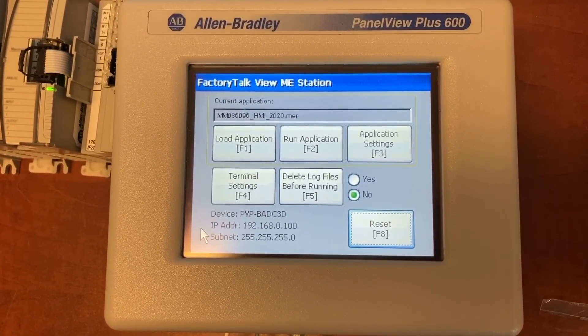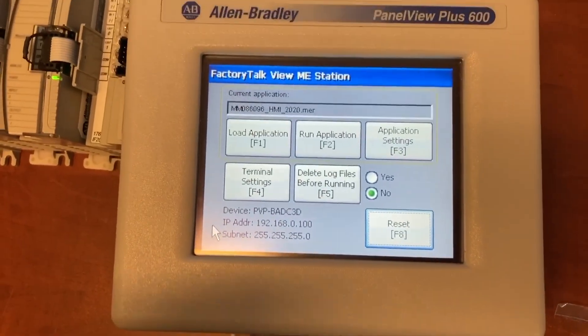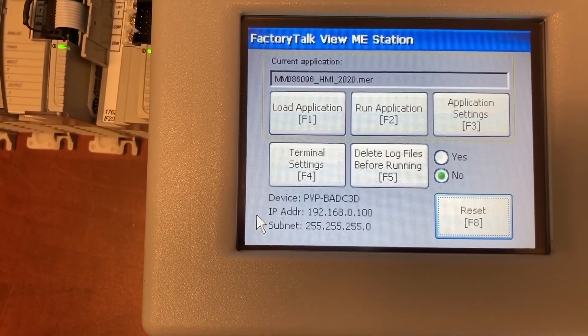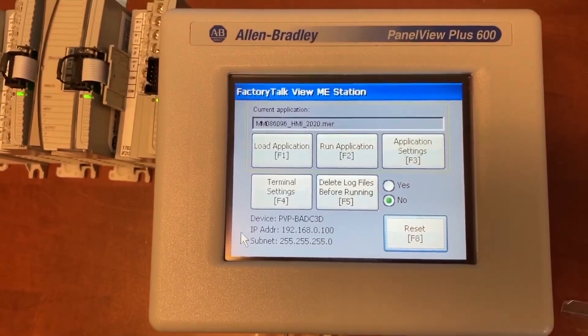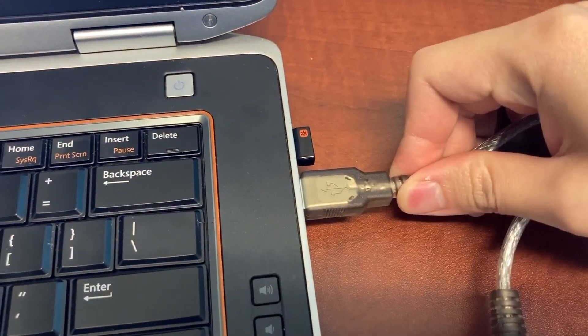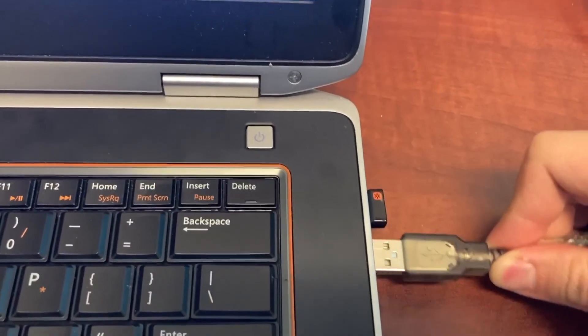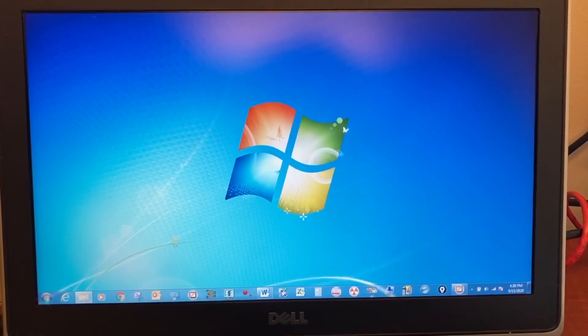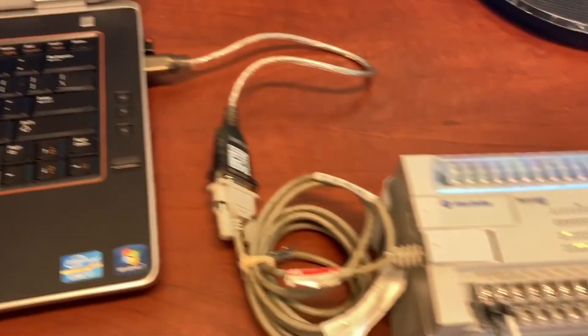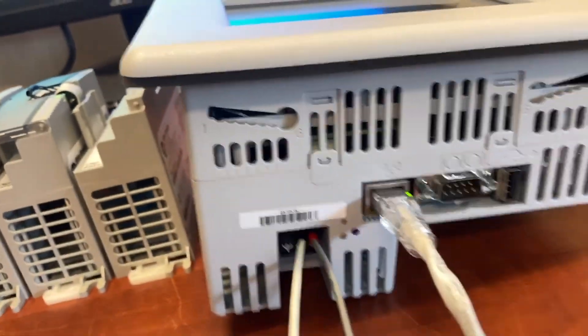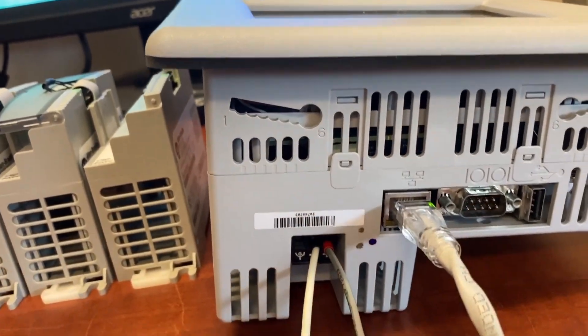On the HMI itself, you will first need to set up the IP address so you can download the program from your computer to the HMI. The IP address for this HMI is 192.168.0.100 and the subnet mask is 255.255.255.0. On the computer, first unplug the USB adapter from the computer and plug it back in. Make sure the PLC is still connected to the computer, and then use the CAT5 cable to connect the HMI to the computer.